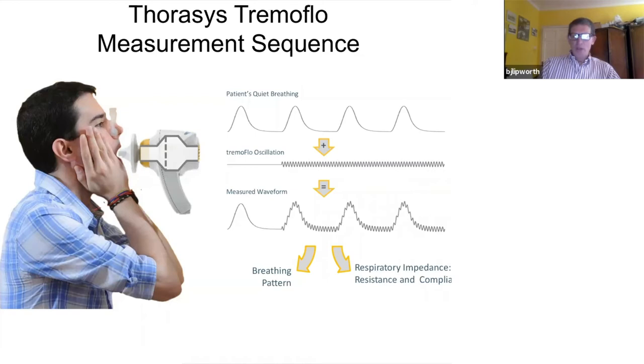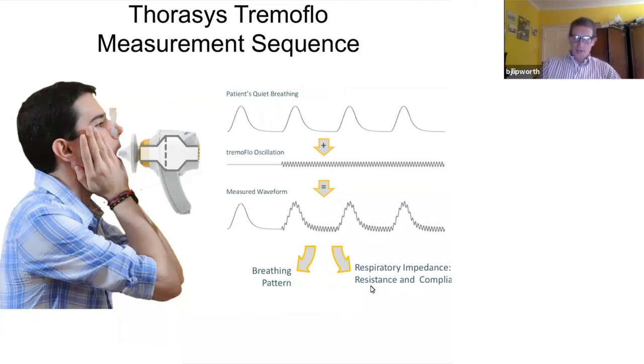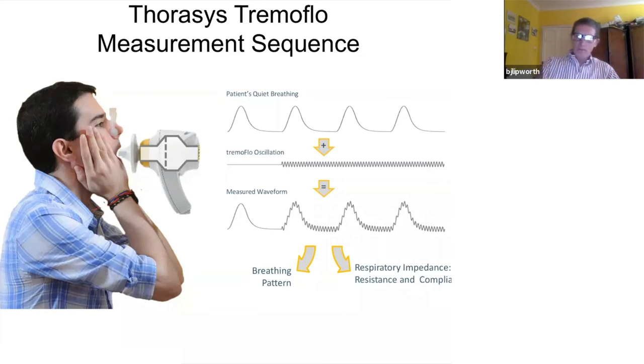That measured waveform generates what we call the respiratory impedance, which is a relationship of pressure to flow. The respiratory impedance has two components: an in-phase component called resistance — exactly what it says — the resistance to airflow; and an out-of-phase component which is the compliance or capacitance of the lung, telling you about the elastic recoil of the lung.